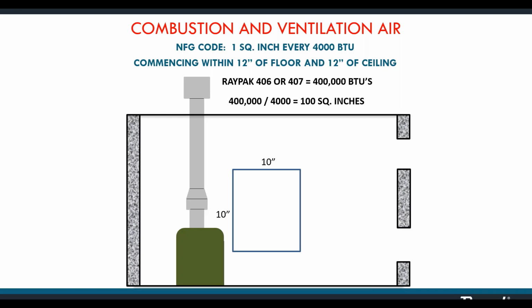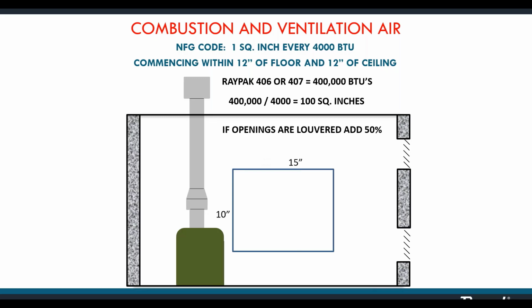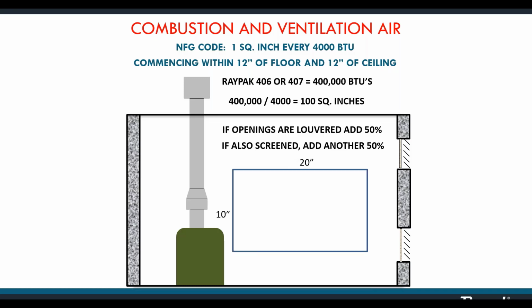So here's the thing about those holes. It's very rare to see these ventilation openings that are just open to the elements. They're usually either covered by louvers or screens or both. All right, those louvers and screens will restrict airflow. So if you have louvers or screens, you would add 50% to the size of that opening. You now have a 10 by 15 hole. If they're louvered and screened, you would add another 50% to the size of that opening. You would now need a 10 by 20 hole. 2 of them, one at the top, one at the bottom.